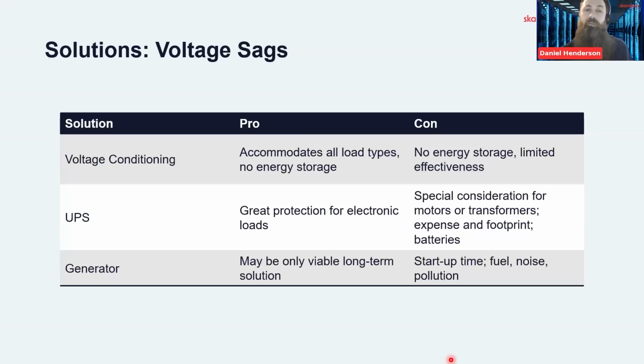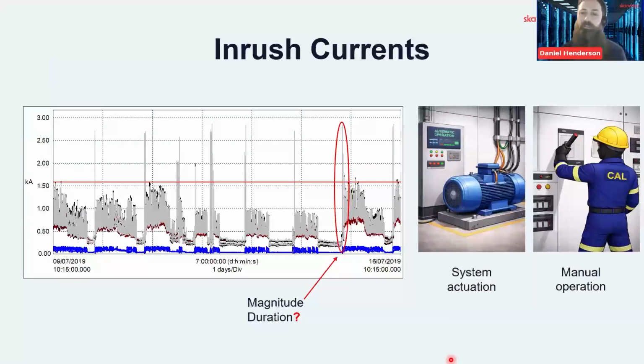causing downtime. And again, with your supply lines, sometimes you have overhead lines, which can have auto reclose functions, and when we've got different weather conditions, that can be an impact if we've got no separate supplies or ride through functions like UPS and things like that. It's about understanding, I guess, whether it's on site or off site that causes the issues, which I'll now lead nicely into Steve's next point.